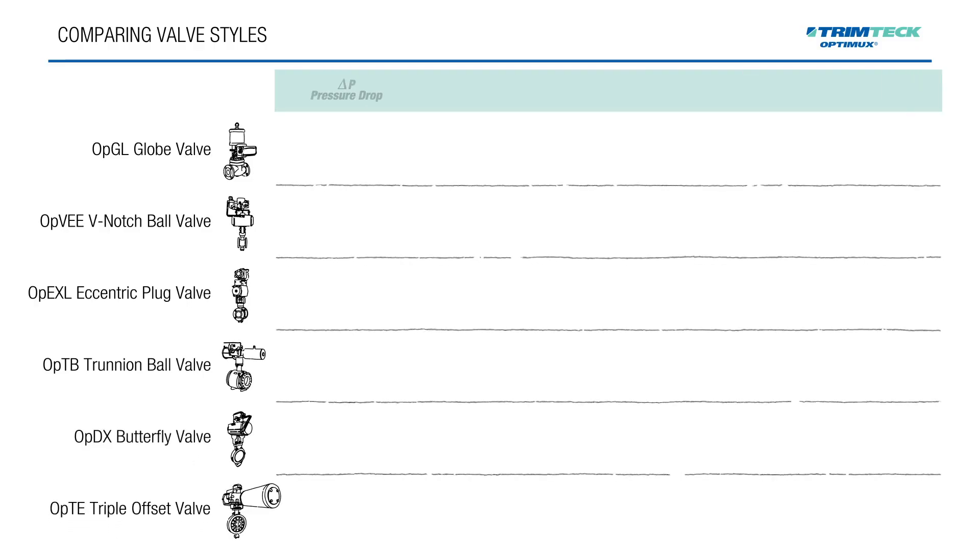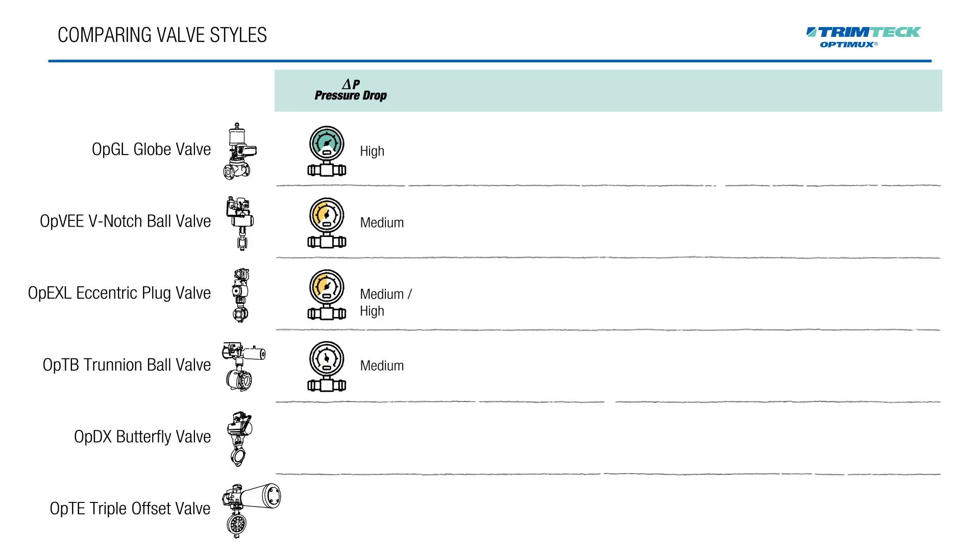First up: pressure drop. Globe valves generally create and tolerate the most pressure drop, making them ideal for throttling applications. As we move toward rotary designs like butterfly and trunnion ball valves, pressure drop decreases. So if your system can't tolerate high pressure drops, a rotary style valve may be more appropriate.